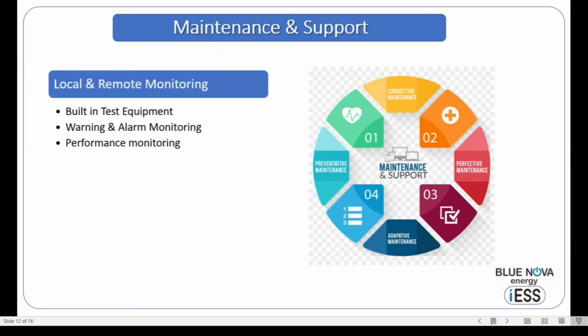Let's talk about maintenance and support. So the system comes with a complete local and remote monitoring capability. It has extensive built-in test equipment which monitors all the parameters of the system. It can then send all the warning and alarm conditions back to the control center, as well as email, WhatsApp, or whatever form of communication is required to send that to the appropriate personnel. And we can also monitor the actual performance of the system, which means the charge efficiencies, discharge efficiencies, the total energy that is cycled, and can have a comprehensive overview of how the system has performed on a day-to-day basis.